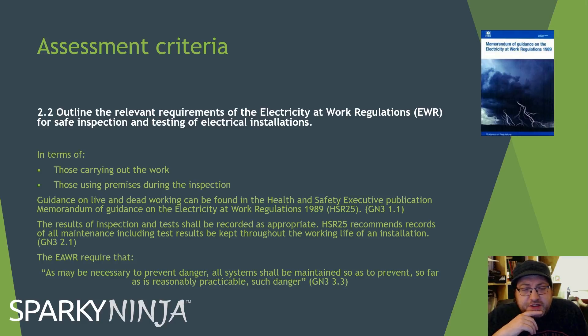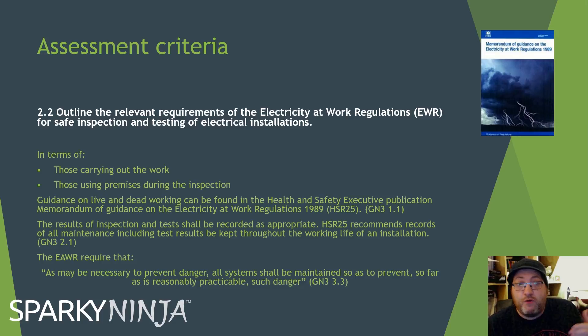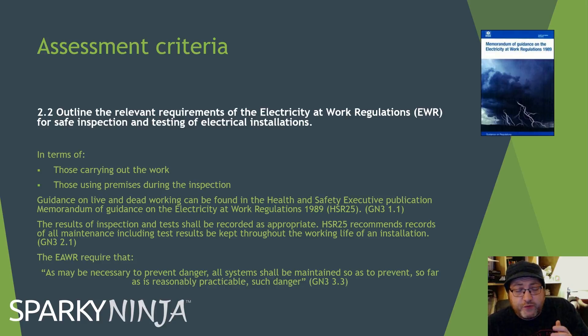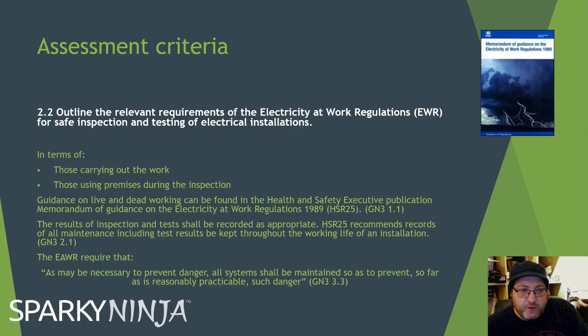Those using the premises during the inspection is something you need to consider. If you're working on a site and going to open up panels or do insulation resistance testing — creating potential differences within the system — you've got to identify risks to persons at work and either remove them from the area or inform the site's responsible persons of these risks. If you do a pre-site survey at one time of day or shift pattern and then send electricians in on a different day with a different quantity of staff, the risks haven't been properly controlled.